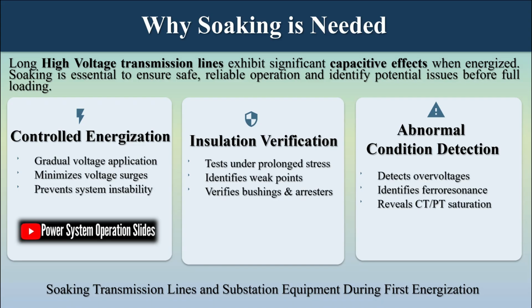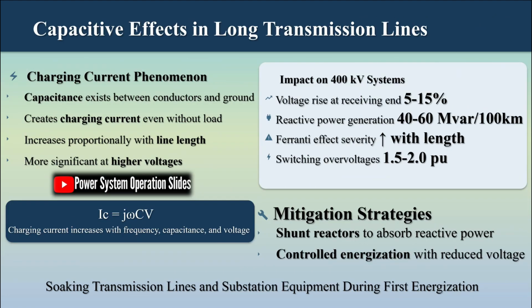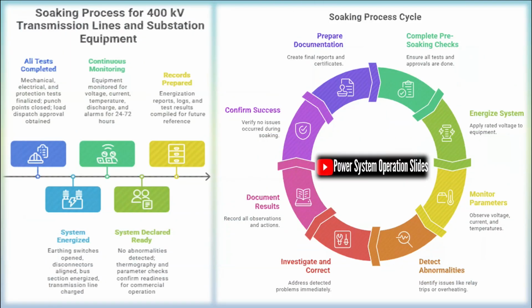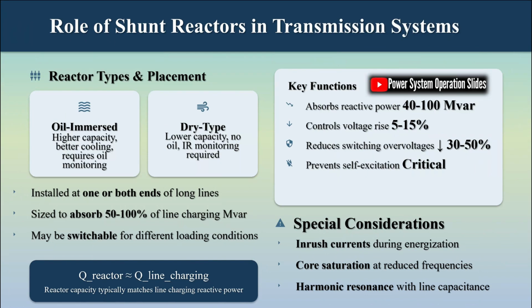This procedure involves applying voltage to the equipment for an extended period under carefully monitored conditions to verify insulation integrity, stabilize electrical components, and identify any hidden defects that could lead to premature failure. Although often overlooked by non-specialists, soaking is a fundamental engineering practice that contributes significantly to the reliability, safety, and long-term performance of high-voltage assets. The purpose of soaking is not simply to energize equipment before placing it into operation.